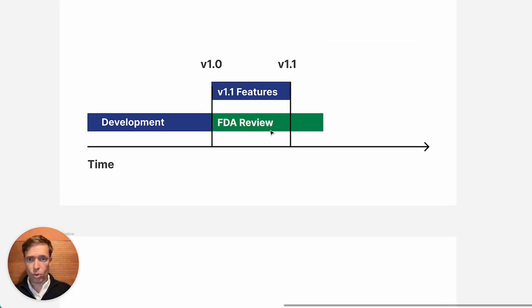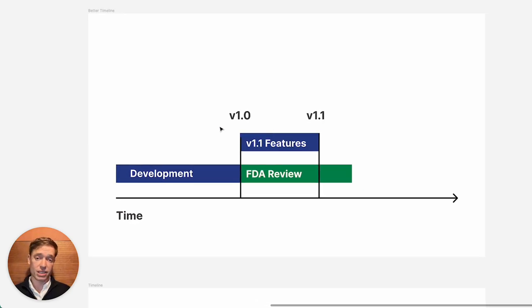One approach or regulatory strategy that we've seen to be very effective is to identify features in the software that aren't critical to the safety or effectiveness of the device, and to put those off until last. So we do all the development up to what we call version 1.0. For that version, we take a snapshot and do verification and validation of the software in that state. Meanwhile, the software team is busily working on version 1.1 while the FDA is reviewing the submission for 1.0.